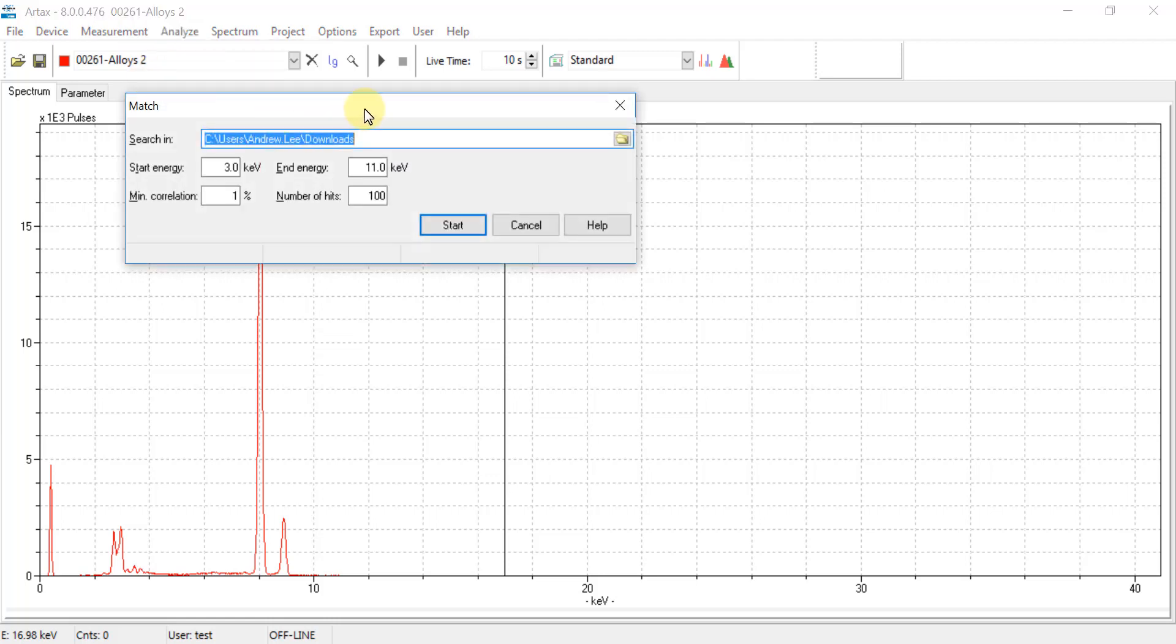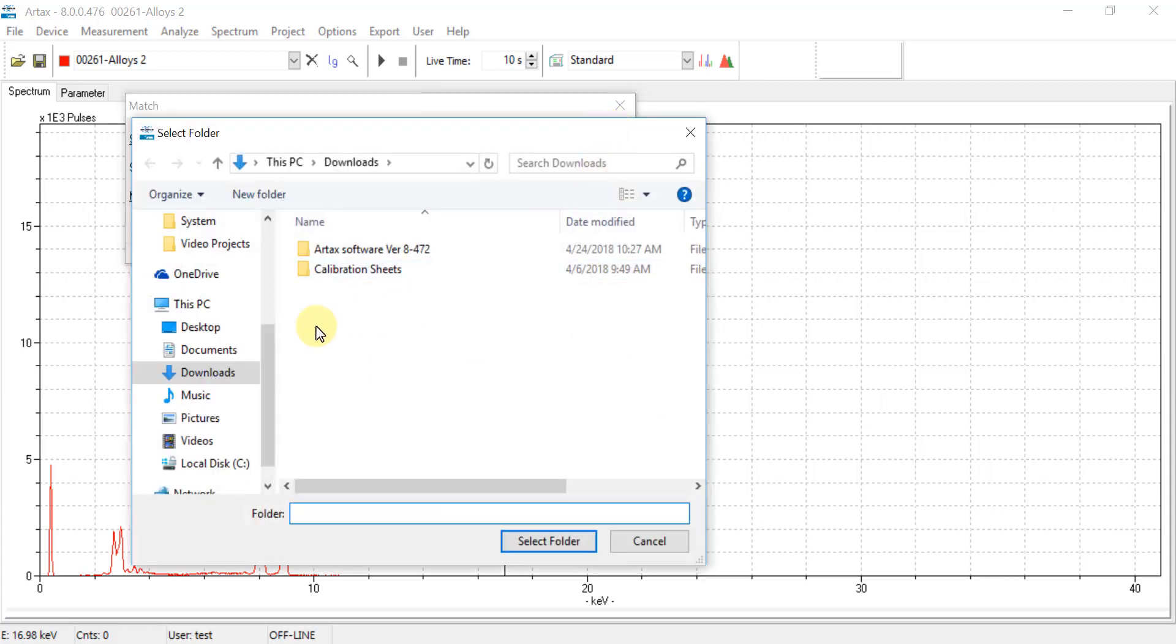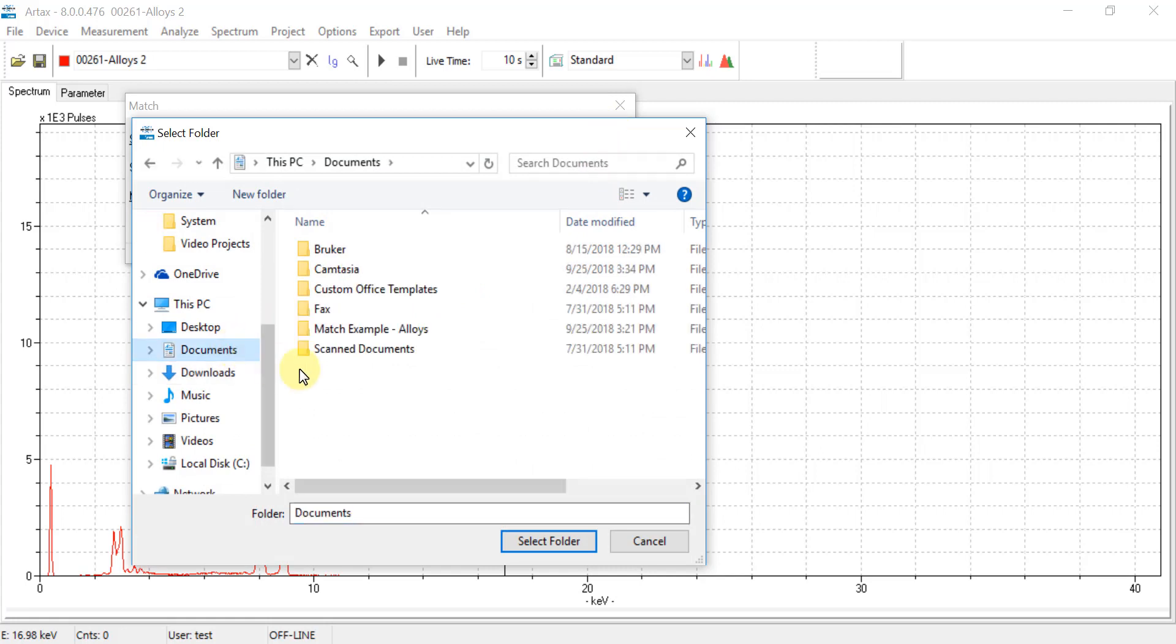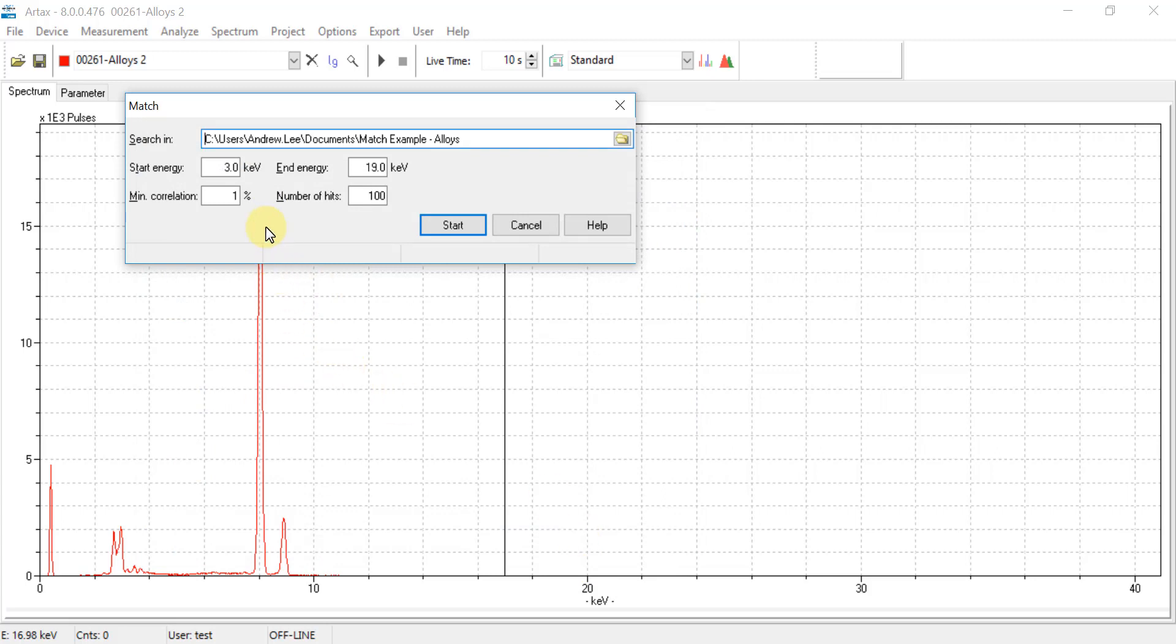From here go to the top menu and select Analyze, then Match. This opens the match settings window. The first step in the match settings is to point the software to the directory where all of the RTX files are saved. This relates directly to how the libraries were saved in the previous step. If they were all stored in one folder then you can point the match routine to that folder and the software will run through all of the libraries. However, if stored in separate folders the user will have to select the individual library to use. To do so, click on the folder icon on the right hand side.